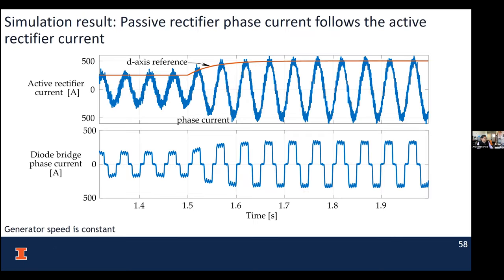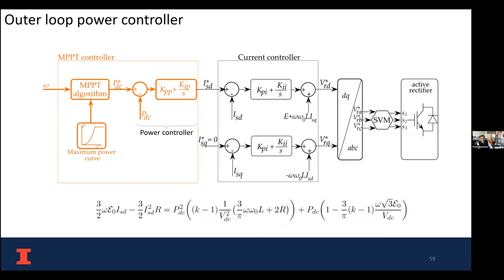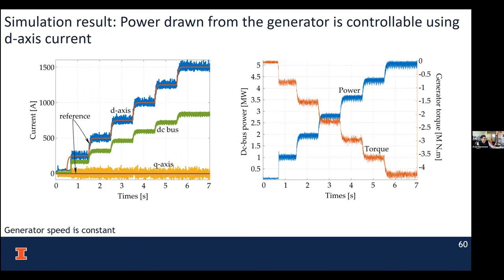You can see in this simulation, as we change the D-axis reference—which governs our active power—the active current goes up, and that's reflected on the passive currents, even though we don't have actual control over them. Now we can wrap up our MPPT controller in addition to these current controllers on the outer loop, and achieve power flow control. As you can see, we can change the D-axis current to match the DC bus current, and based on that we can do step changes in the power as well as the torque.